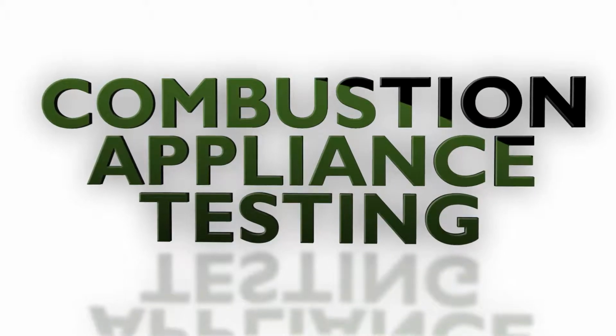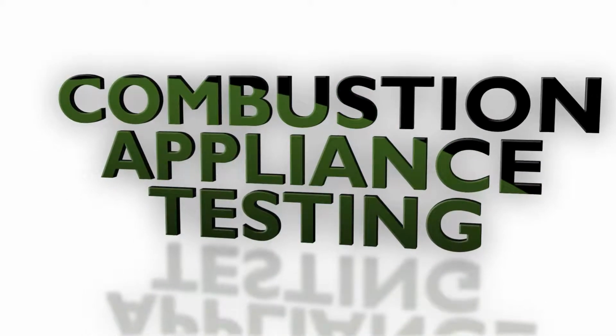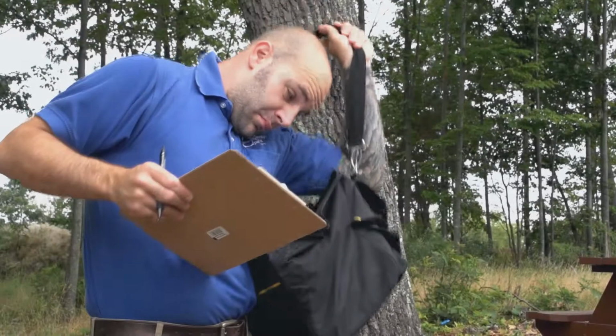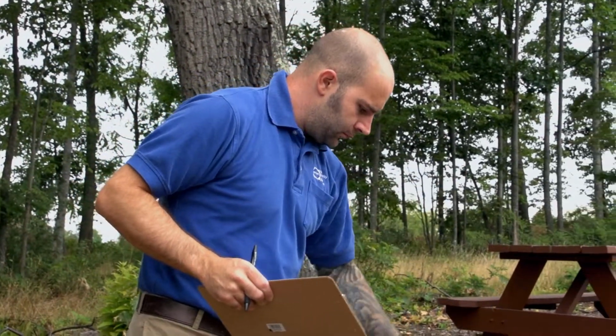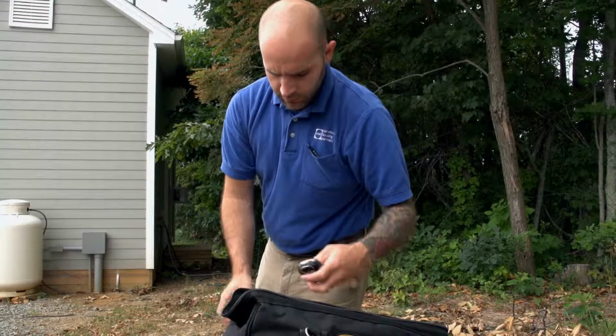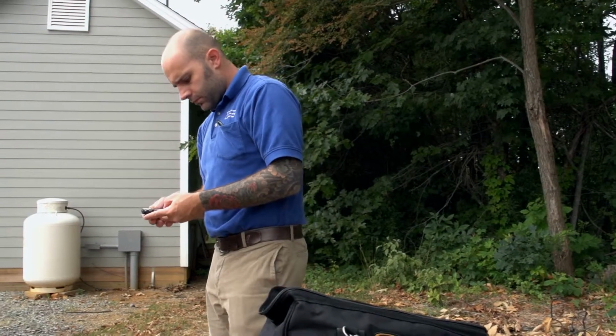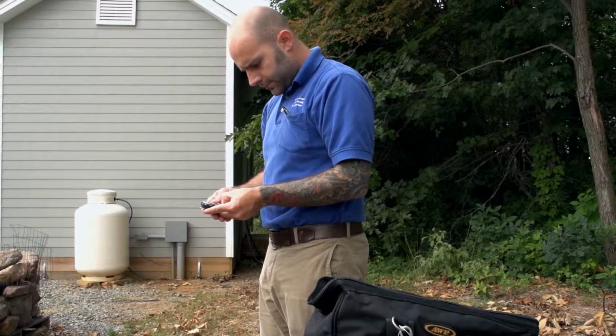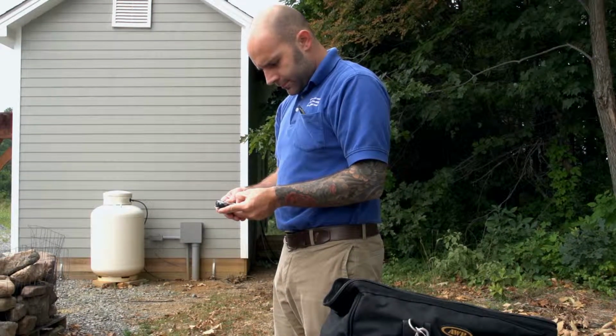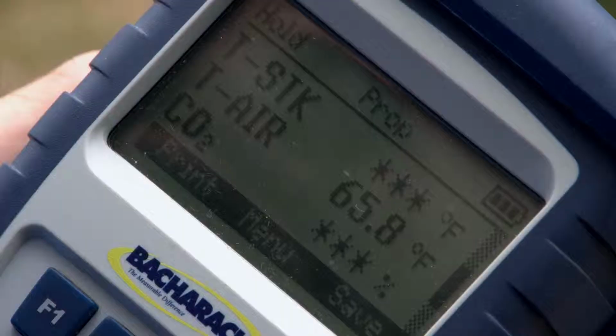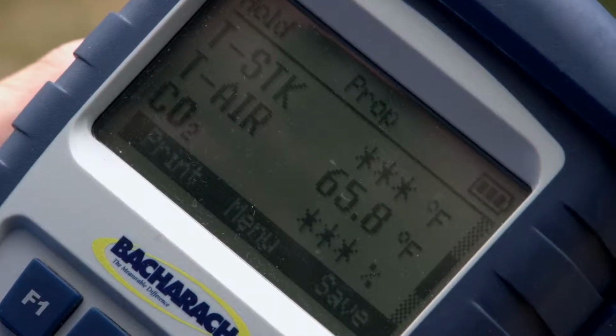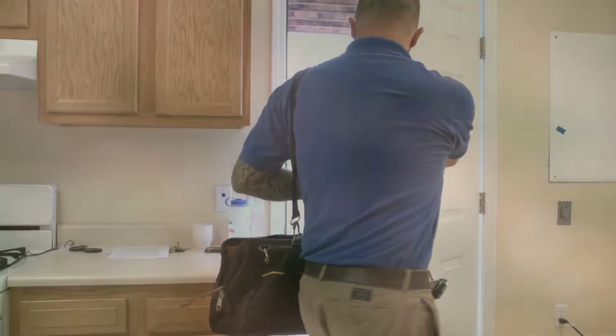After weatherization work has been completed for the day, you must perform a worst-case CAZ test to ensure proper draft before leaving the job site. Calibrate all of your meters outdoors, several feet from the house, in a well-ventilated area void of heavy traffic or other high sources of CO. This includes the personal CO monitor. Check the ambient temperature outside.